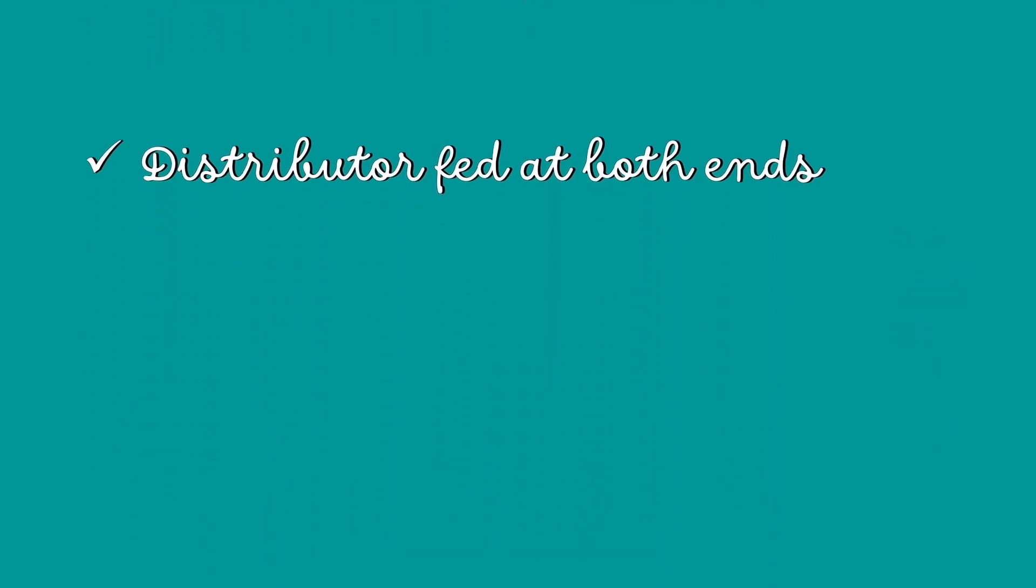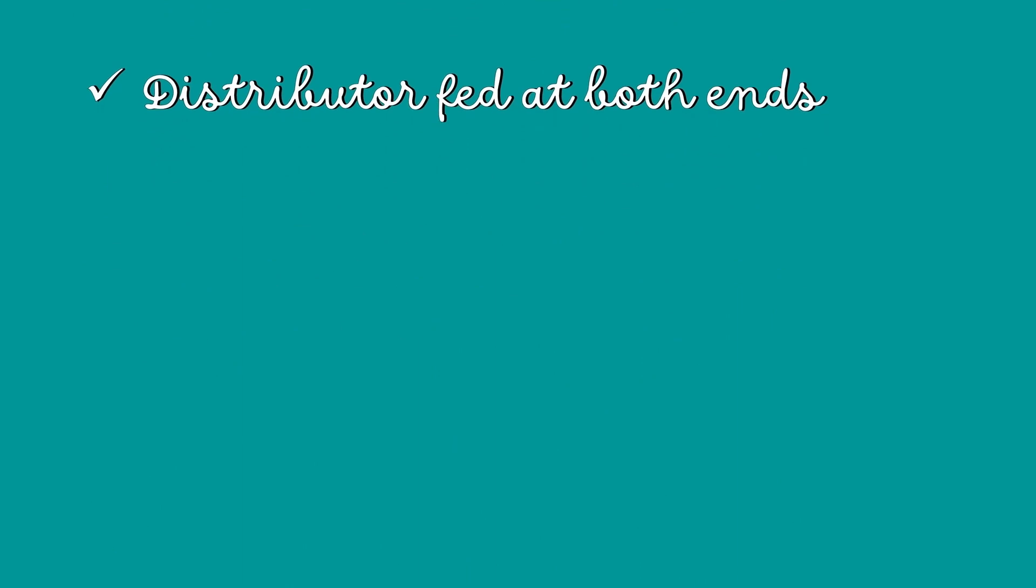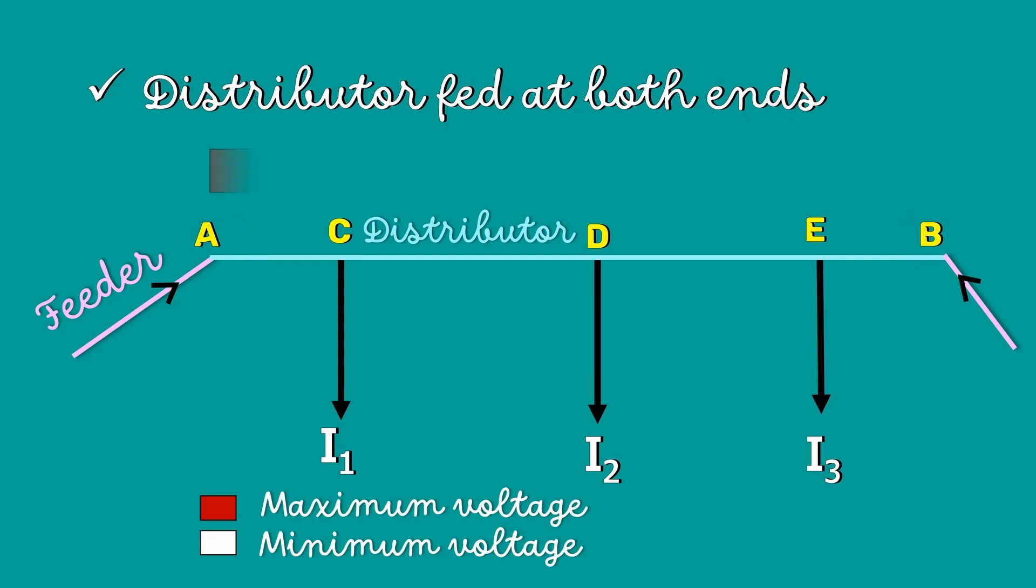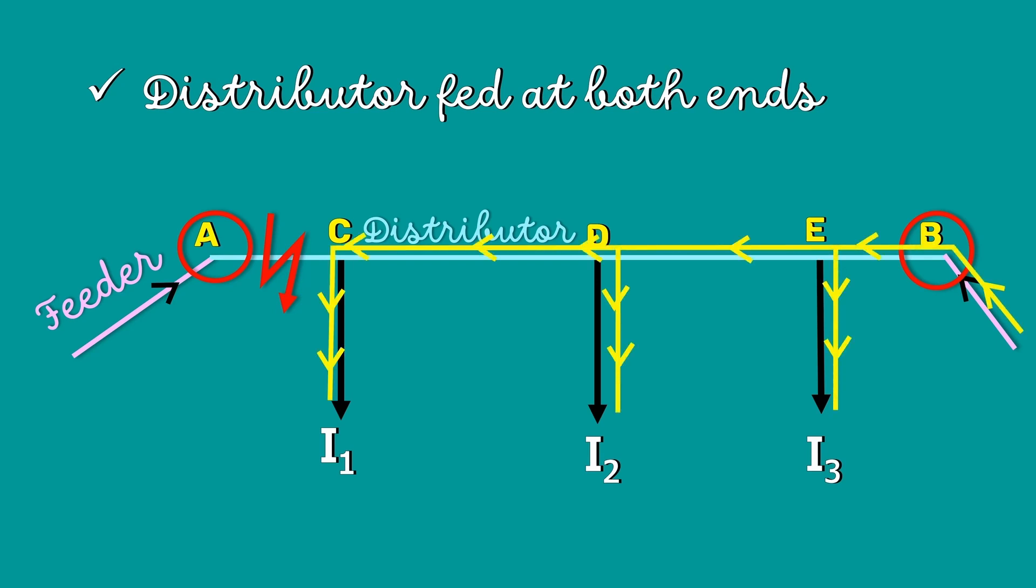The second type is the distributor fed at both ends. In this type, the distributor is connected to the supply at both ends. The voltage at the feeding point may or may not be equal. Here, the load voltage goes on decreasing as we move away from one feeding point, reaches a minimum value and then starts rising and reaches the maximum value. Since the distributor is fed at both ends, in the case of fault, the continuity of the supply is maintained.